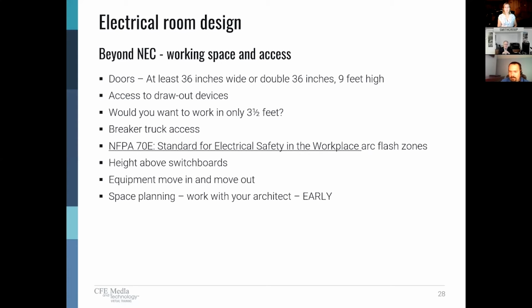About the 3.5 feet that's in those tables we talked about, on some of the bigger 800 amp panels, 1200 amp panels, would you really want to work in 3.5 feet? Again, those are minimum standards. Unless it's absolutely essential, try and look at 4, 4.5, even 5 feet where you can in primary electrical rooms, not necessarily secondary. You want to be able to get breaker truck access in. Truck access is when you draw out those breakers in a switchgear, and you've got to lift a heavy breaker out and get that out. That also goes through the doors and down the corridor.